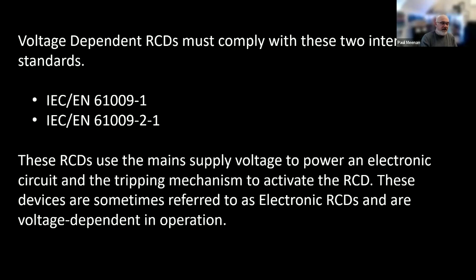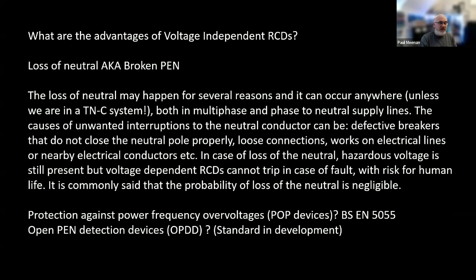Then we have voltage dependent, which require compliance with 61009, 1, 2, and 1. These RCDs use the mains voltage to power an electronic circuit and the tripping mechanism to activate the RCD, so they're referred to as electronic RCDs and are voltage dependent. The majority of RCDs out there are electronic ones. The older ones, it's always been said, will work if you have a loss of neutral, because if you lose the mains and you still have some energy there and there's a fault, you can potentially still operate that device.